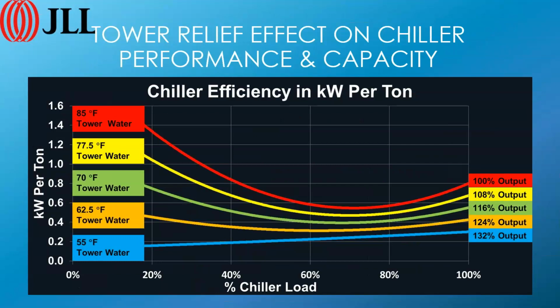So why do we do that? Well, with 85-degree tower water, you can see the sweet spot in the middle is right around 70% or so at 100% output. Well, with 55-degree tower water, we got 132% output. There's no reason for us to stage up at 70% anymore. There is no sweet spot. So if we had 55-degree tower water, we would run one chiller all the way up to 132%. We'd run that 1,000-ton chiller up to 1,300 tons and let it run all day. It'd be very happy, wouldn't be overcurrent, no problems with the chiller, nice good delta T, everything's fine.